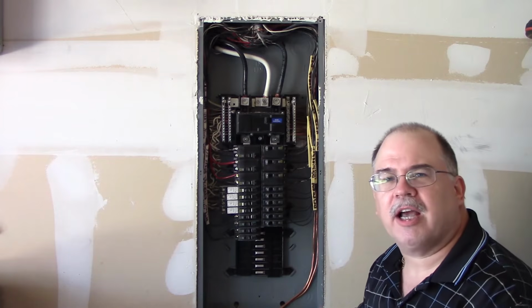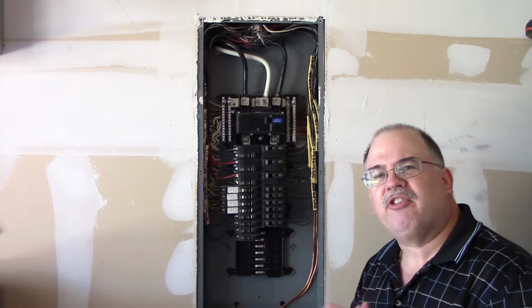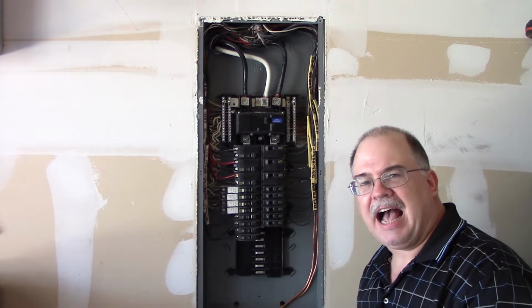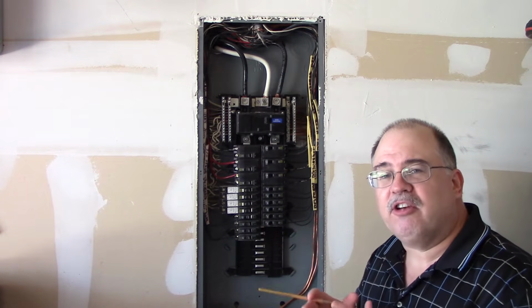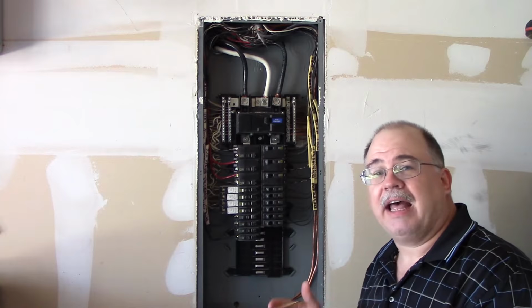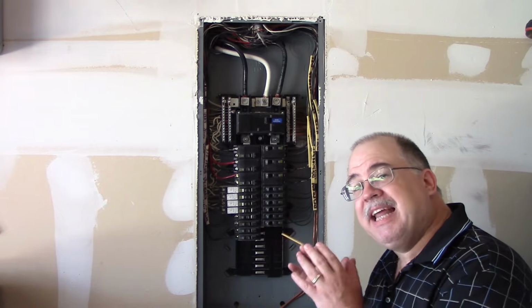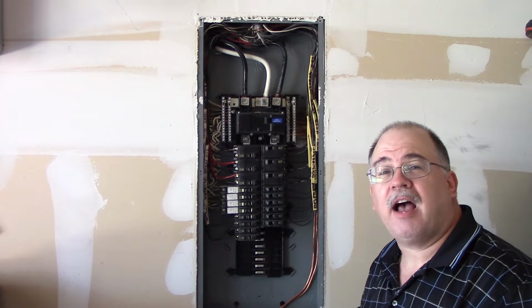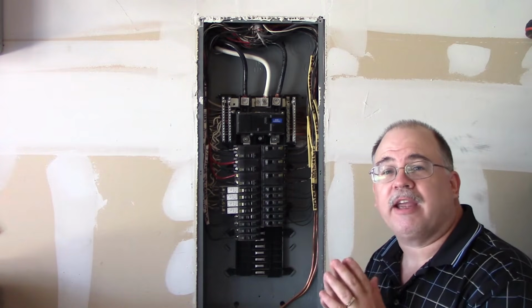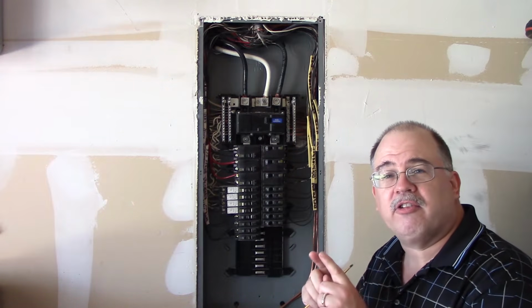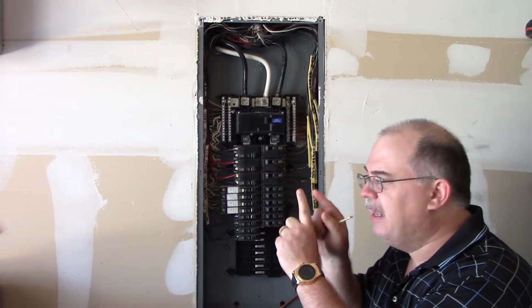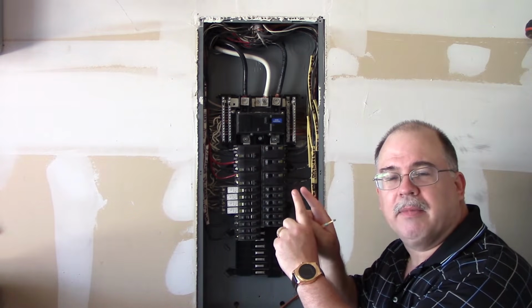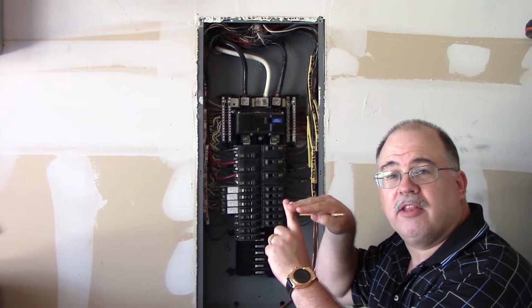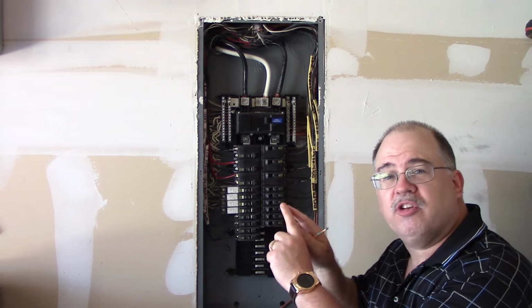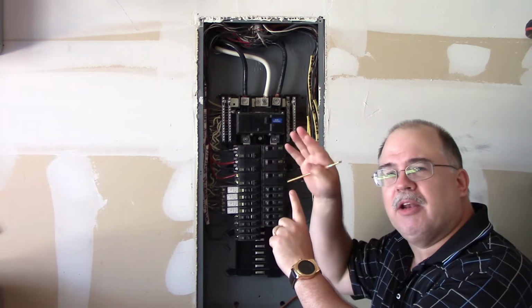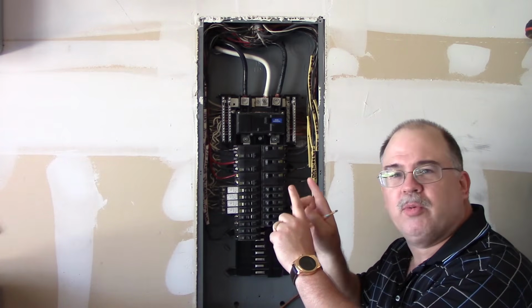Now, a little bit of a lesson on the combination. What is that? A combination is not a combination AFCI and a GFCI. Okay, that is a dual function device. So let's clear that up right away. Basically, what combination is, it detects combination, parallel, and series arcing events. So a parallel condition might be 2 conductors that are side by side that have an arc because of damage between them, an extension cord, what have you, that gets caught in the door in your house, somebody's running it through a jamb or whatnot. There is no limit on the load here. It is simply an arc between conductors.